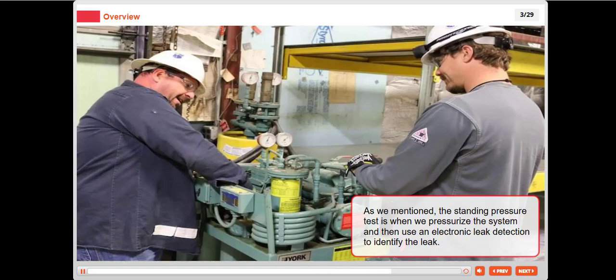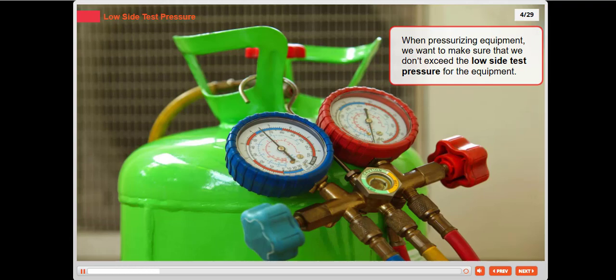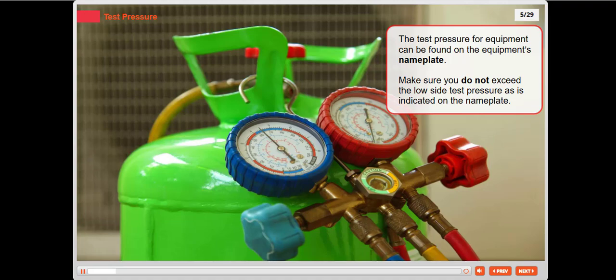When pressurizing equipment, we want to make sure that we don't exceed the low side test pressure for the equipment. The test pressure for equipment can be found on the equipment's nameplate. Make sure you do not exceed the low side test pressure as is indicated on the nameplate.